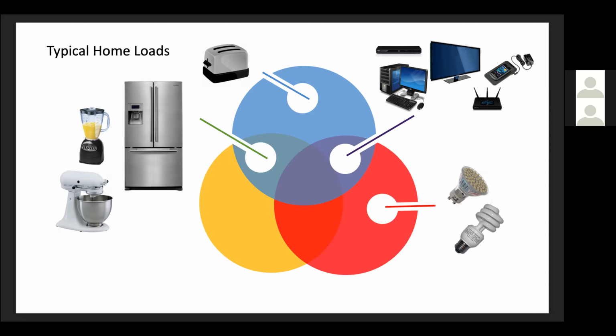CFLs, fluorescent lights in general, and gas discharge lights fall completely within that transient load characteristic circle, the red circle here. They should absolutely be avoided if at all possible, because most people are not going to have the type of equipment to measure what those transients are in order to plan that backup load. So it's best to keep those to the bare minimum and/or eliminate them whenever possible.